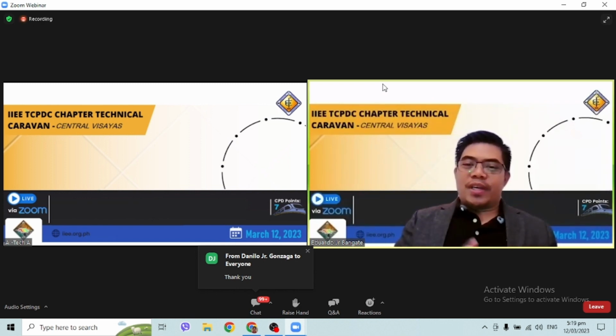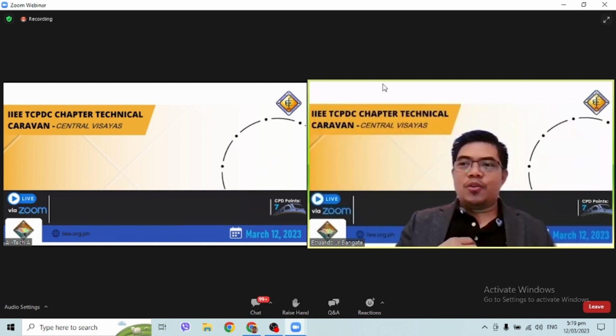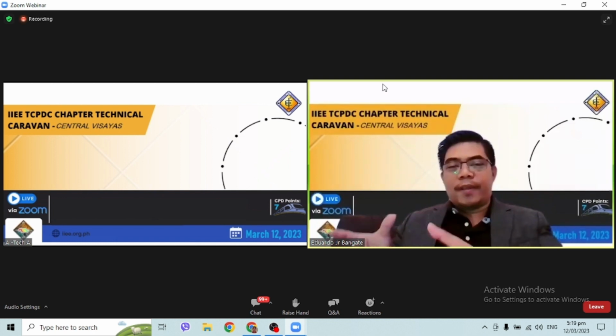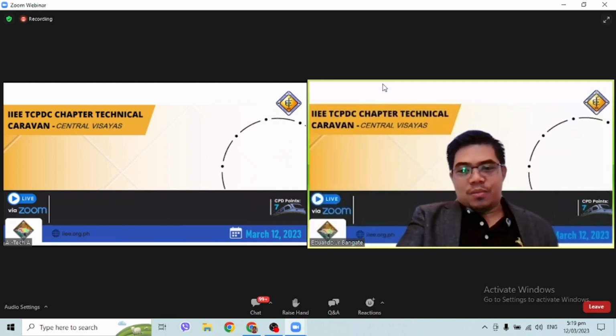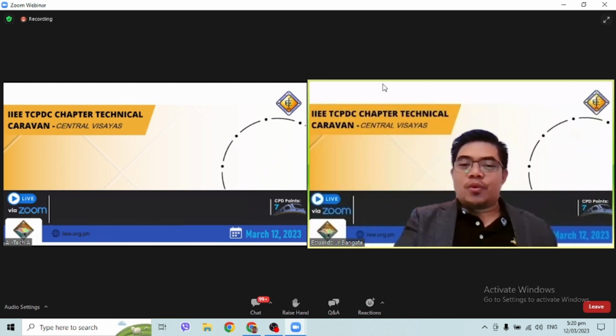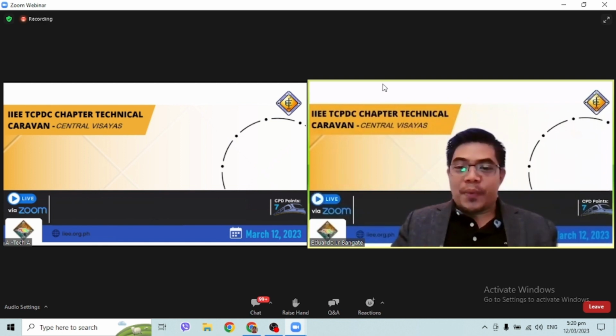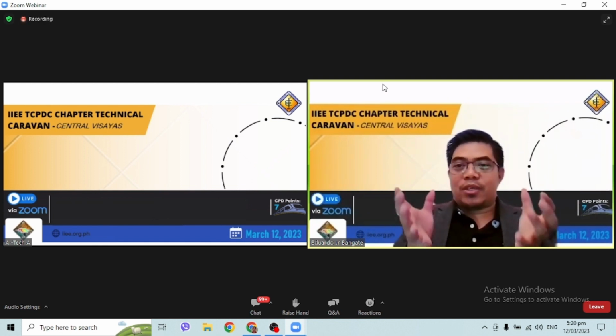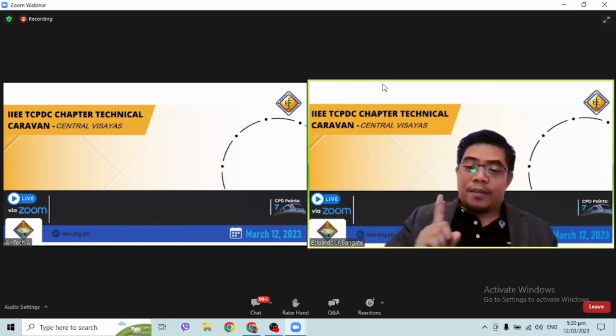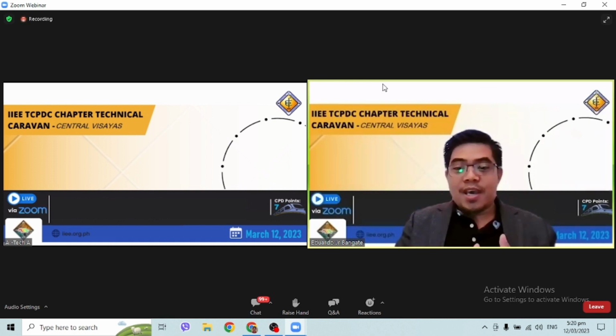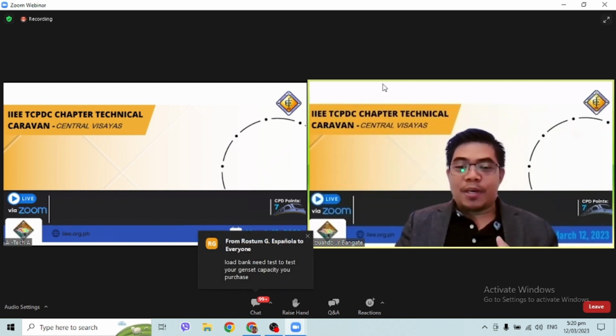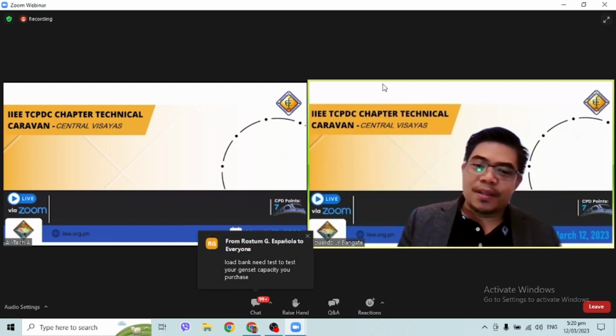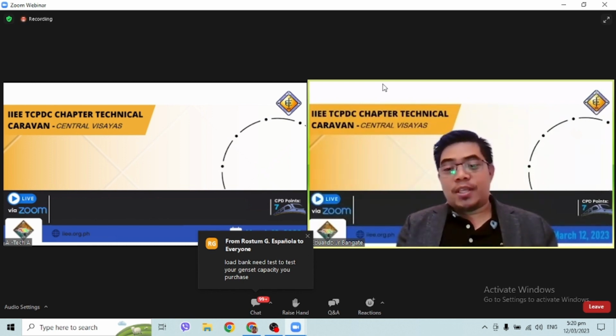Because when you order a generator, for example, I am the customer. If I order a 100 kVA generator, then I need to make sure, before I put it into the generator room, which is not easy, that this generator is really capable of carrying what they promised. For example, a 100 kVA generator should be able to carry 100 kVA. Sa load bank test, ginagawa ang 100% testing. Minsan 110% testing, depende kung ni-require ng customer. Sinabi nila, gusto ko 110% test on resistive load.